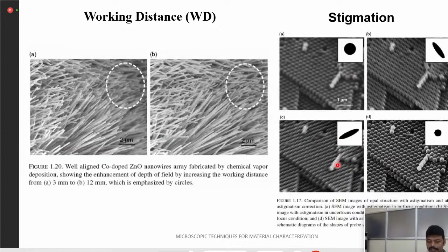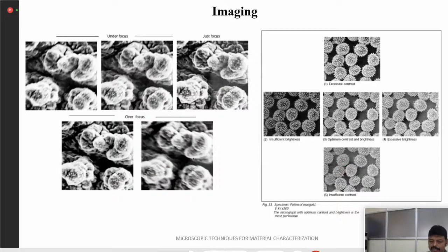Then it is very important to adjust the contrast and brightness. Automatic brightness and contrast control is there in the system. Still, we will adjust the contrast and brightness by our own hand. And then focusing. When we are doing the analysis hands-on with multiple samples, we get an idea of how to focus. Here you can see an under-focus image, an over-focus image, and a just-focus image. We should capture the focused image and adjust the contrast and brightness. That is also very important.